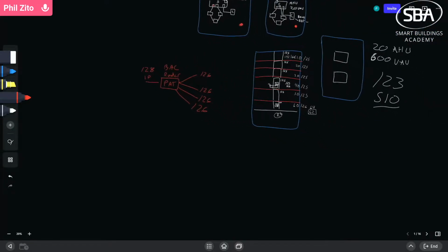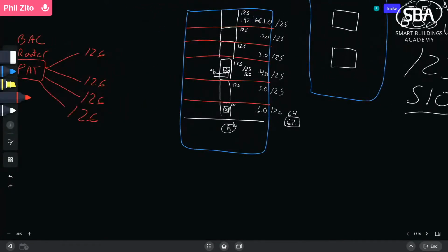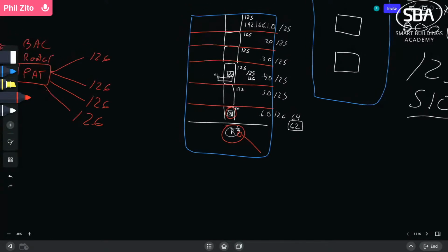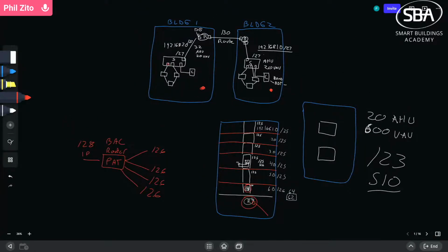An additional thing that I see a lot of people do is they provide this infrastructure right here. They provide the switch, they provide the router, and then they have a single port here which connects to the customer's IT network once the customer actually goes live with their network. These would be industrial switches and industrial routers that you would put in place during the construction process. So this was a lot. I hope it gave you a baseline understanding of what the architectures look like.